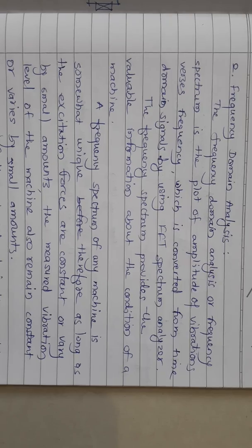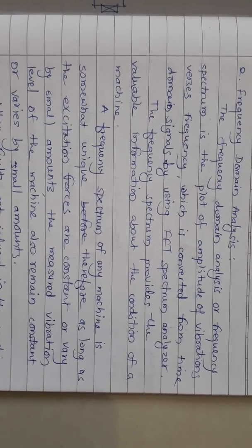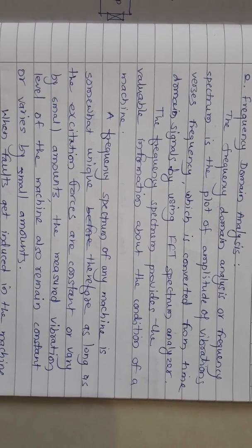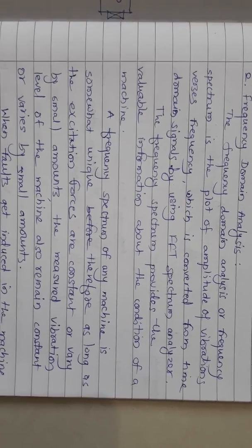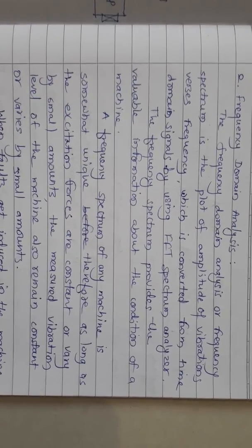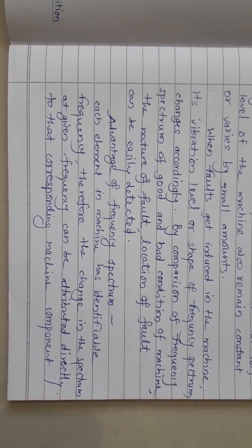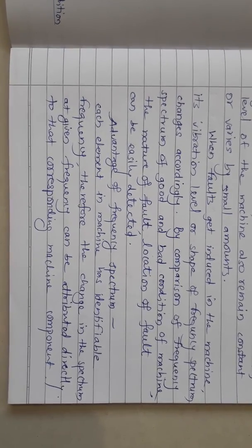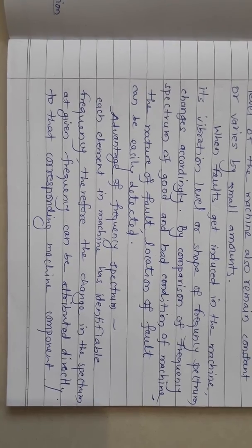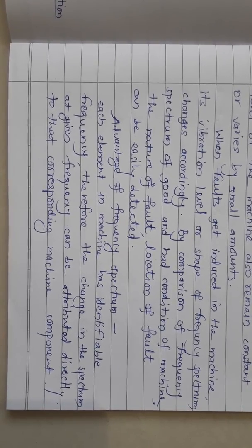Frequency domain analysis: the frequency spectrum is a plot of amplitude of vibrations versus frequency, which is converted from time domain signals by using an FFT spectrum analyzer. The frequency spectrum provides valuable information about the condition of a machine. The frequency spectrum of any machine is somewhat unique; therefore, as long as the excitation forces are constant or vary by small amounts, the measured vibration level also remains constant. When faults get induced in the machine, its vibration level or shape of frequency spectrum changes accordingly. By comparison of frequency spectrum of good and bad condition of machine, the nature and location of fault can be easily detected.